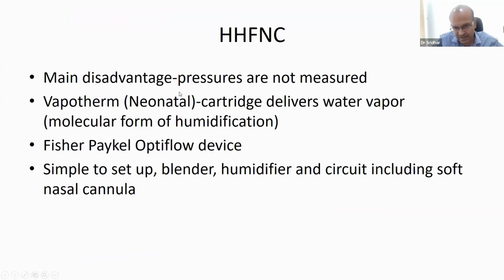So the main disadvantage of high flow, and the reason most of us are not keen on using it as a primary mode, is because the pressures are not measured. You're guessing the pressure. In CPAP as well, you can argue that it's not really that the pressure is measured. We think that's the pressure reaching the baby, but there are many variables like the way the snug fit is there. If the baby is opening the mouth, the pressure drops as well. And if there are secretions in the airway, the nasal passage isn't clear, the pressure doesn't reach the lungs. So this is a relative disadvantage. But the main disadvantage is that the flexibility, the amount to which you can increase the pressure, is lower with high flow, especially because we follow a limit of 8 liters for newborns.